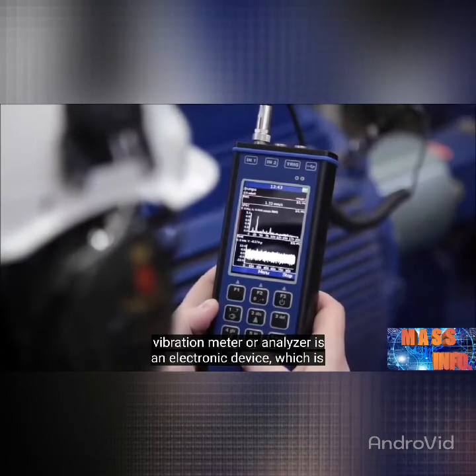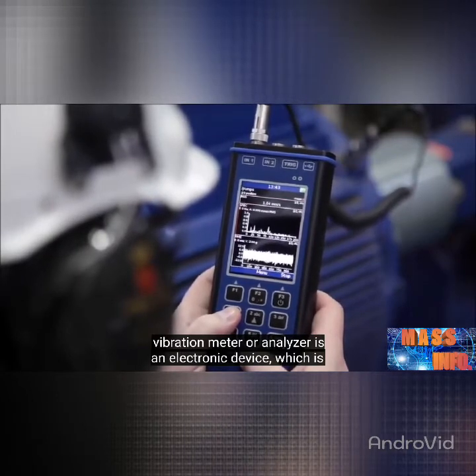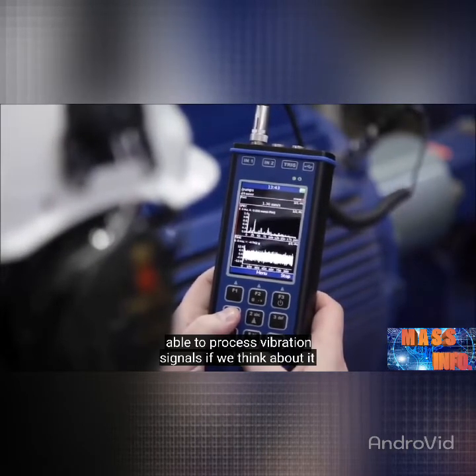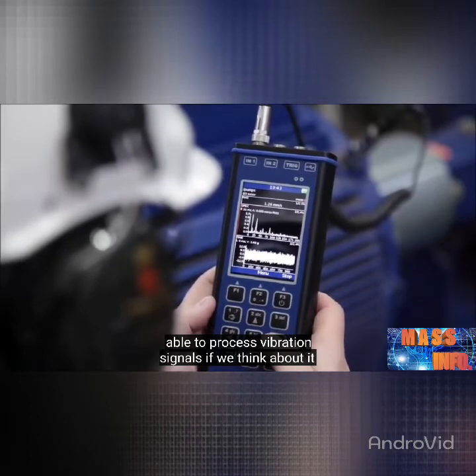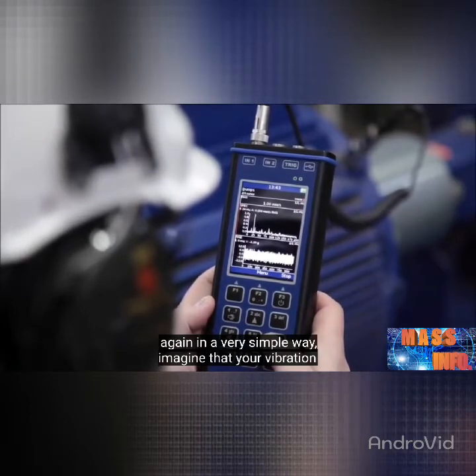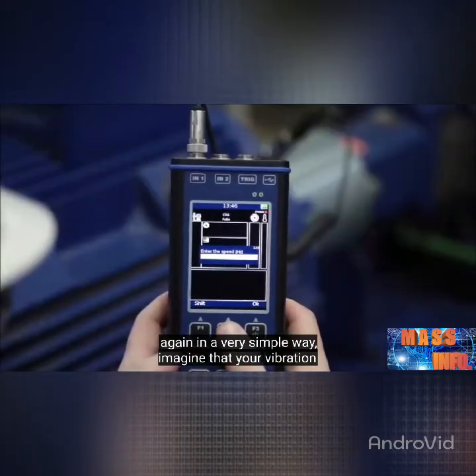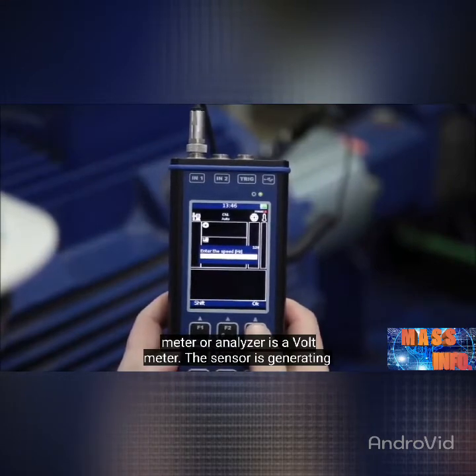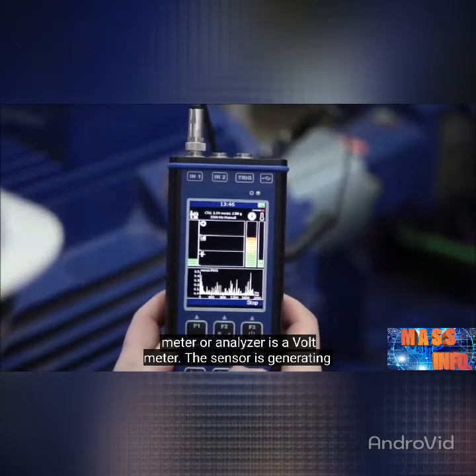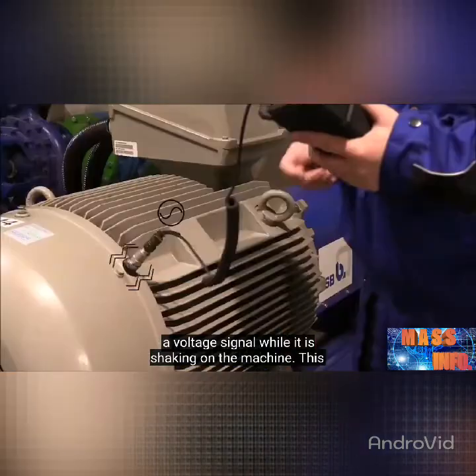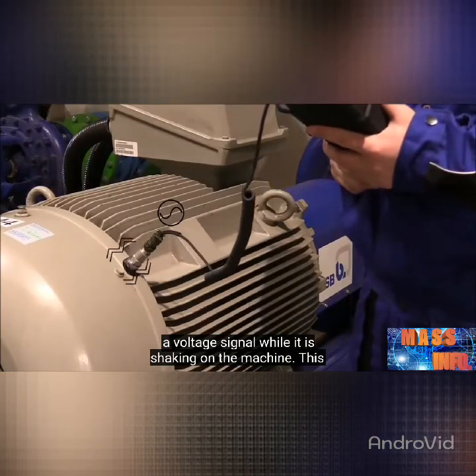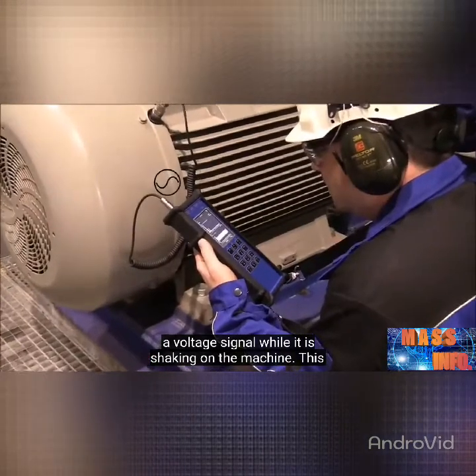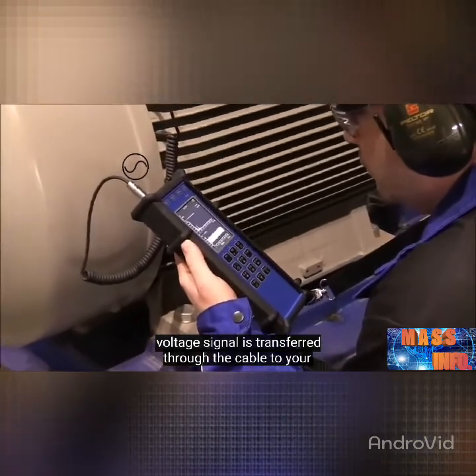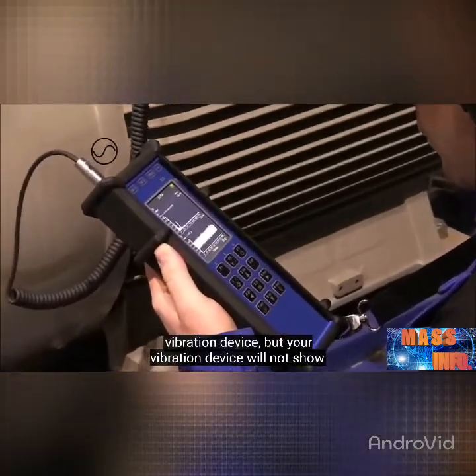A vibration meter or analyzer is an electronic device which is able to process vibration signals. If we think about it again in a very simple way, imagine that your vibration meter or analyzer is a voltmeter. The sensor is generating a voltage signal while it is shaking on the machine. This voltage signal is transferred through the cable to your vibration device.